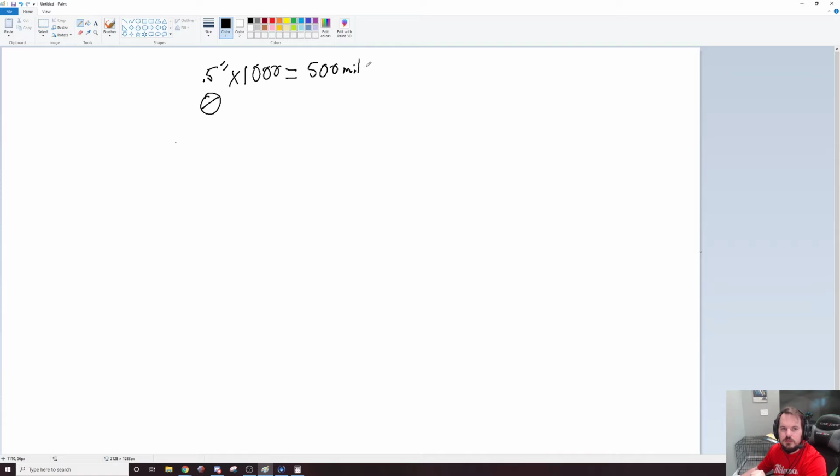500 mils. And then now that you're in mils, you take the diameter in mils squared, and that will give you your area in circular mils.